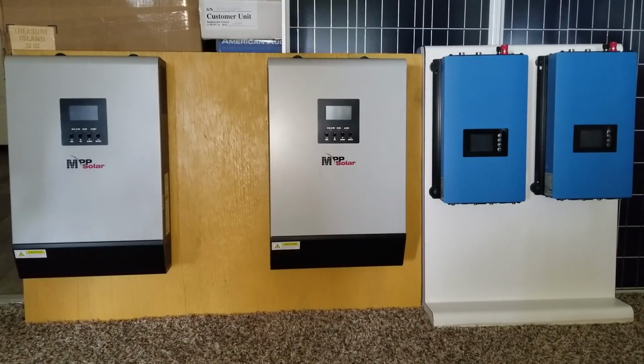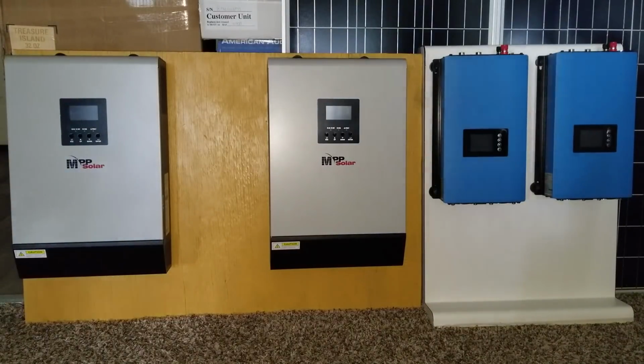Just remember, you don't have to go more than 65 volt input. Those inverters can serve your purpose. You can tie them to your split phase, to L1 and L2, so each inverter attaches to one leg of your breaker. That means this grid-tied 1000 inverter goes on one side of the leg, and the other one goes on the other side of the leg.